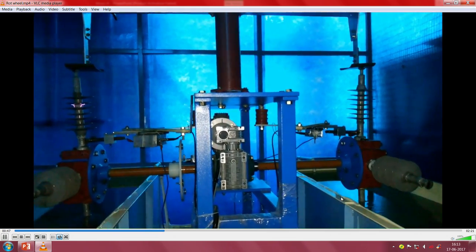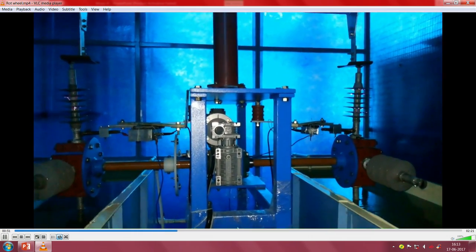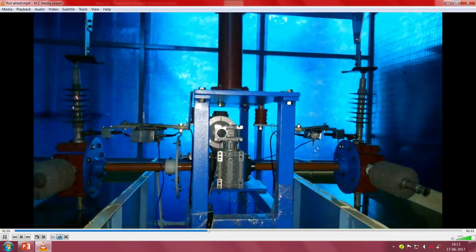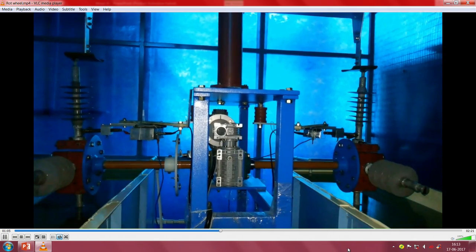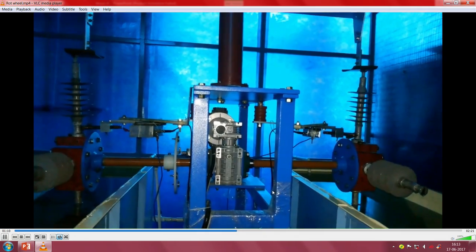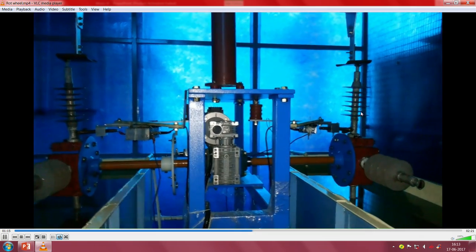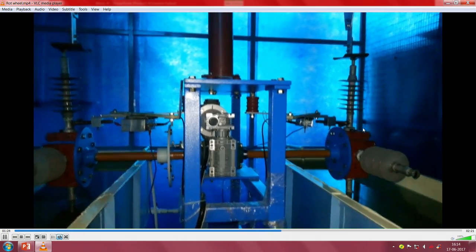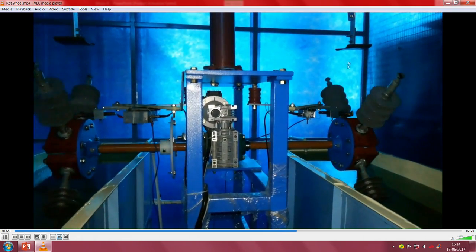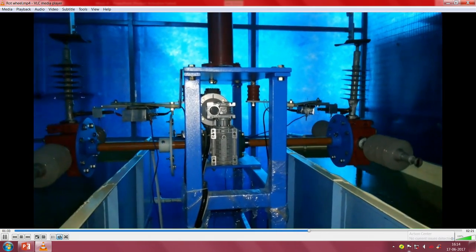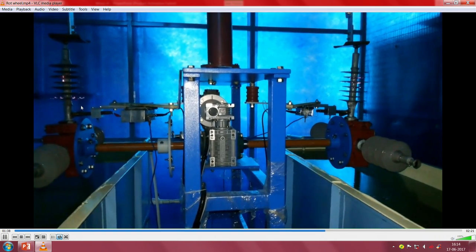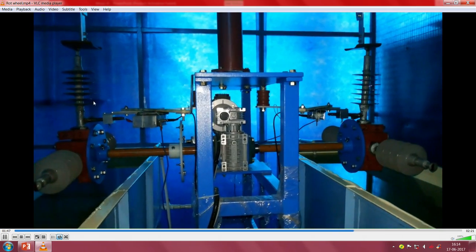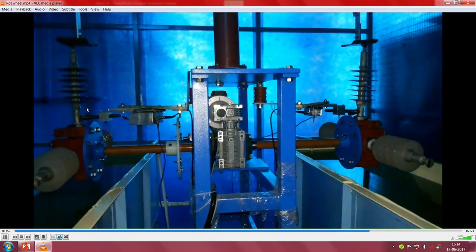This cycle of rotation and voltage stress is continuously applied for 1000 hours. During the experimentation, leakage current on both sides is measured using the shunt box with protection, employing a digital storage oscilloscope and National Instruments module to capture data for the entire 40-second high voltage contact period. After 40 seconds, the next insulator in line comes in contact with the high voltage — the transition is 8 seconds. Initially, due to surface wetness, several discharges occur; later, as the surface dries under stress, the discharge activity and leakage current flowing on the surface decrease.